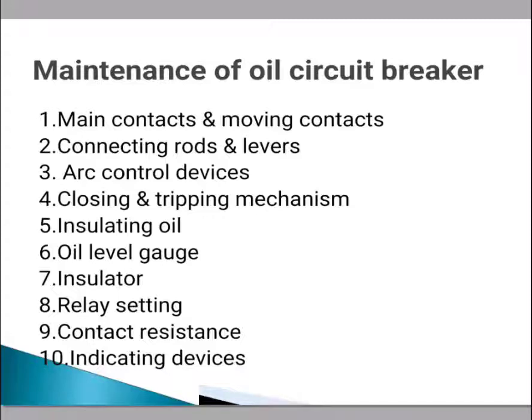For the arc control device, check for carbon deposits. If deposited, remove them with a blunt-edged tool and wash the surface with kerosene oil. Replace the burn plates and replace the whole assembly for better performance.